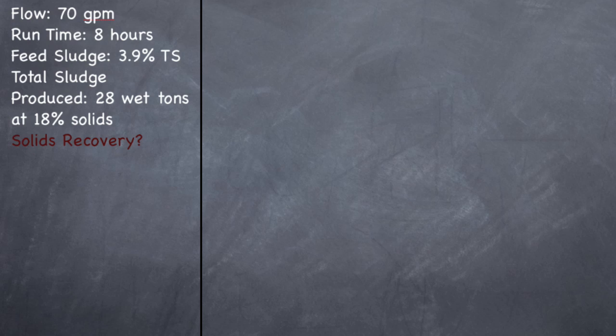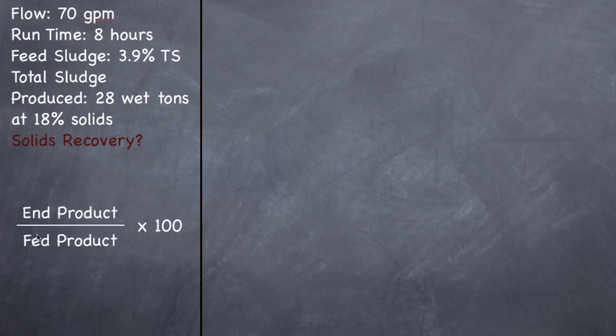Percent efficiency for a belt press is the end product divided by the fed product times 100. So we need to find out how many total pounds we fed, and then how many total pounds we got out of it. Let's go ahead and start by doing that.